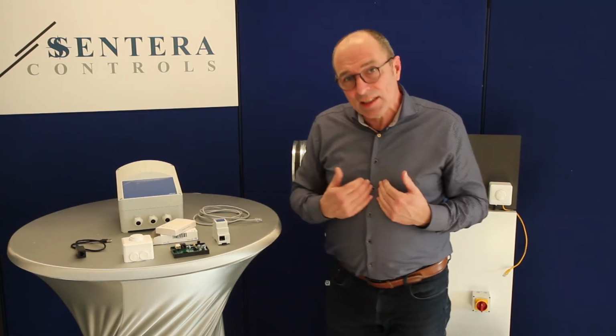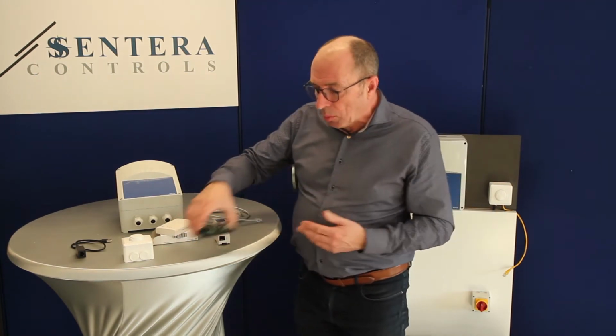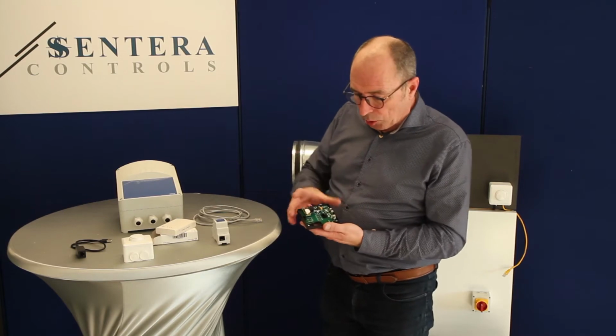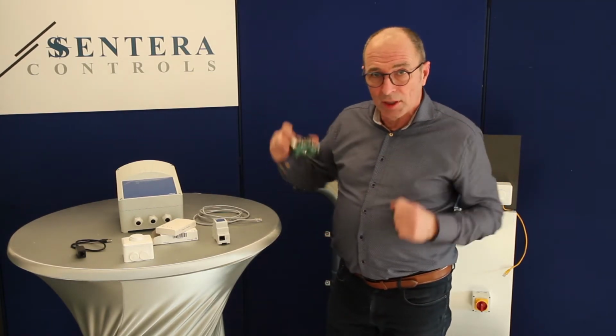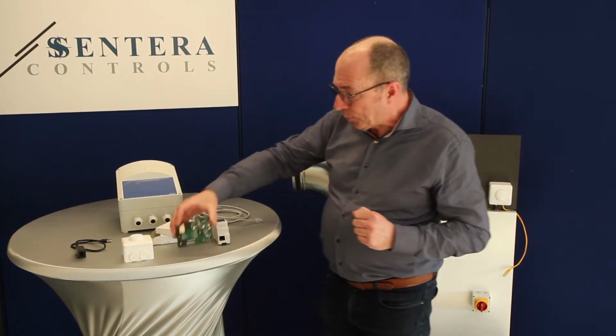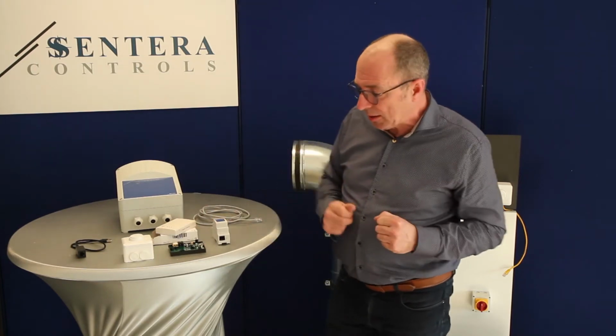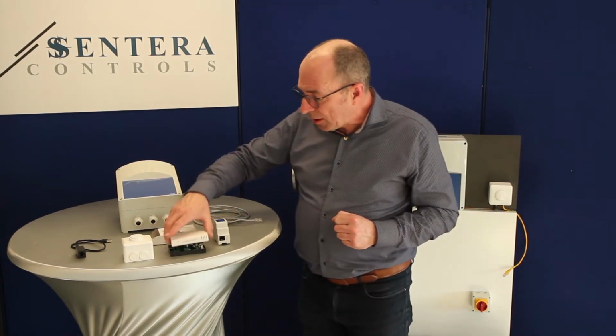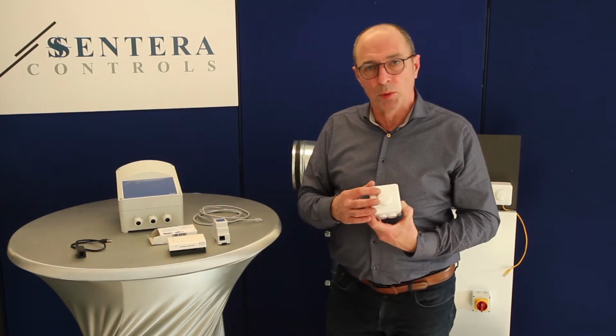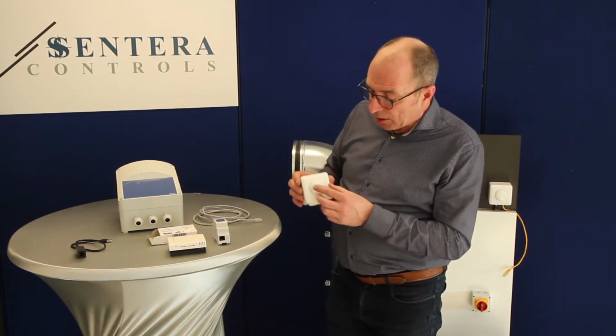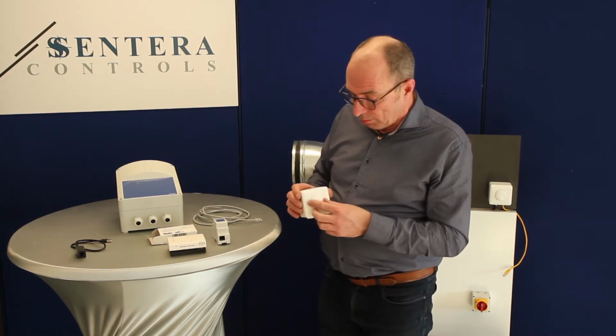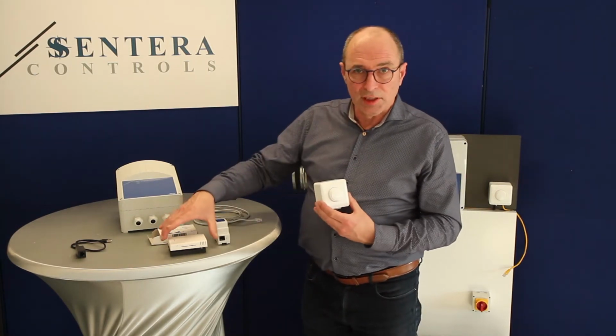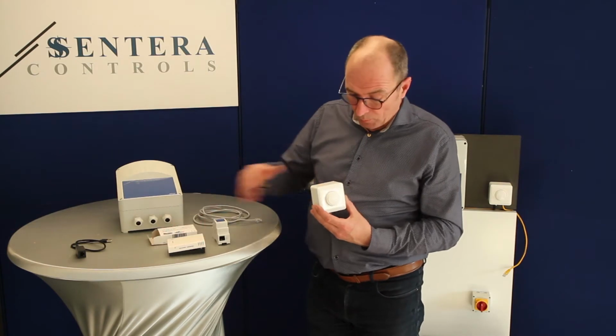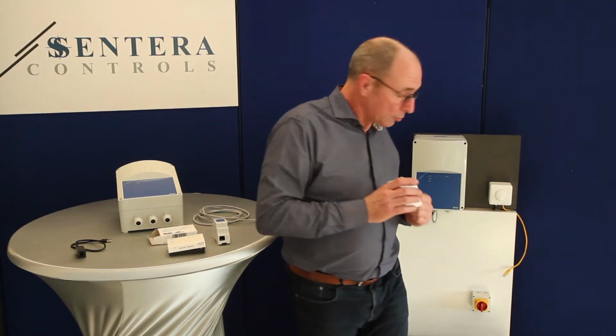For demonstration purposes, it is of course difficult to simulate a nicely moving CO2 curve right now. Therefore, we should be able to make additional CO2, which is not the case. Well, Sentera nowadays also has potentiometers equipped with a Modbus output. That actually means that by turning the knob, I can simulate the output value of a sensor. We're going to do this in a moment in this setup.